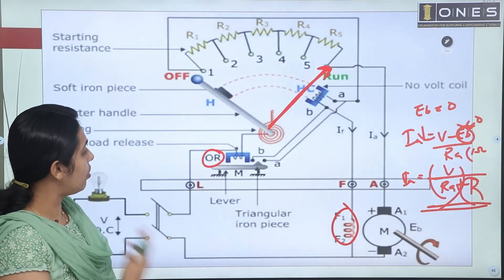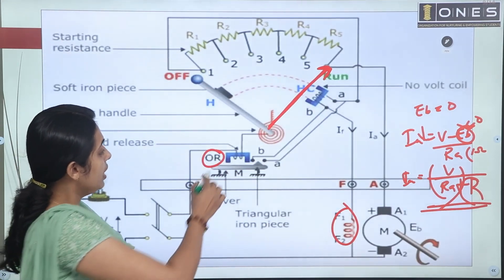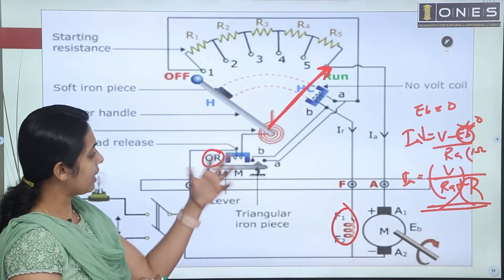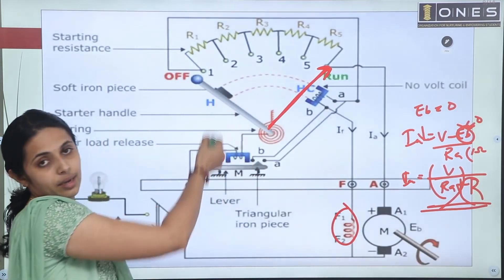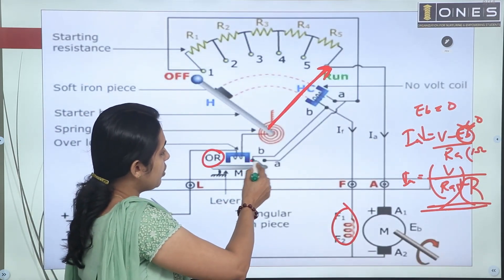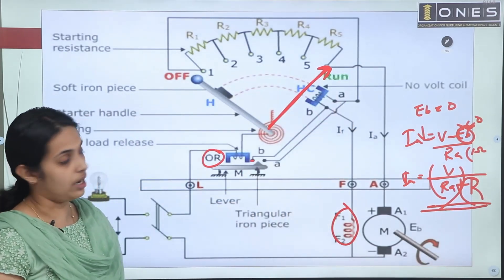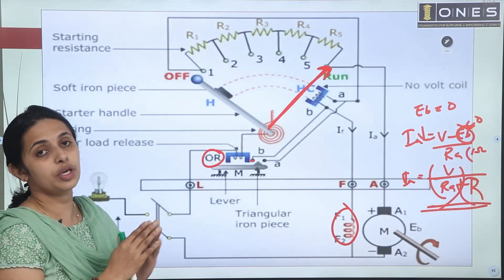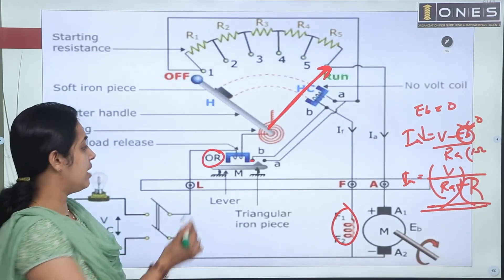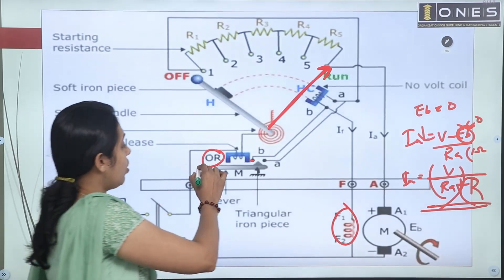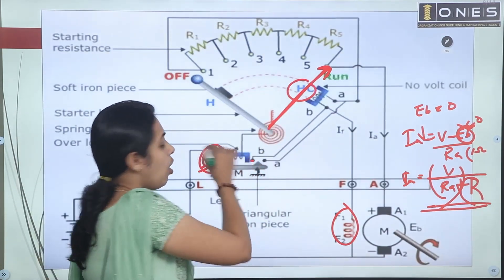The other protective function is the overload release coil. In the case of overload, a magnet attracts the armature, short-circuiting the holding coil terminals, which de-magnetizes the holding coil. The spring returns the arm to off position, protecting the motor. So the 3-point starter has two coils: the holding coil and the overload release coil.